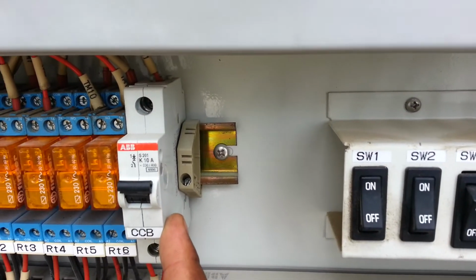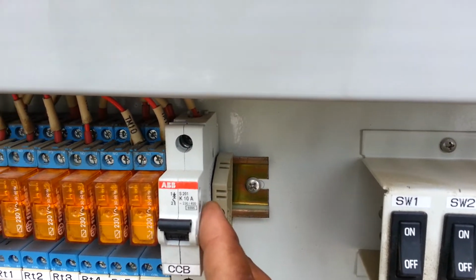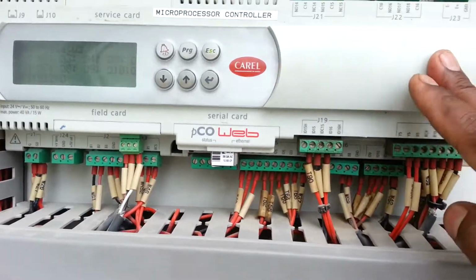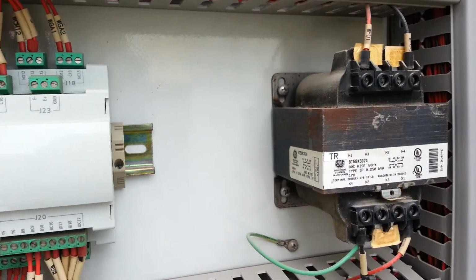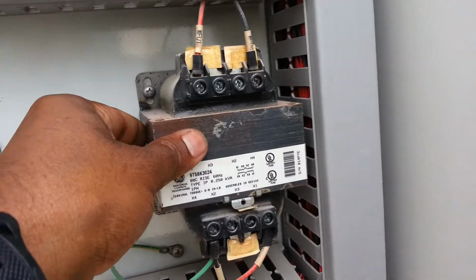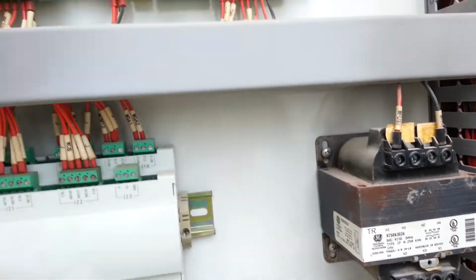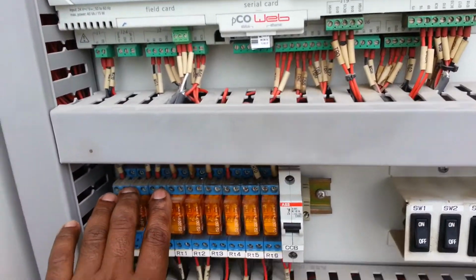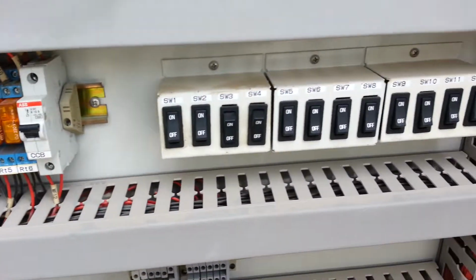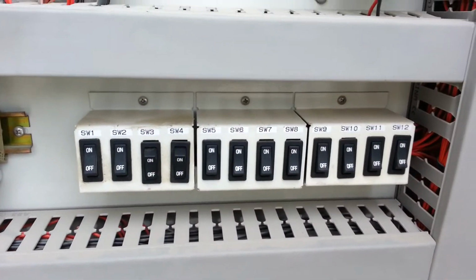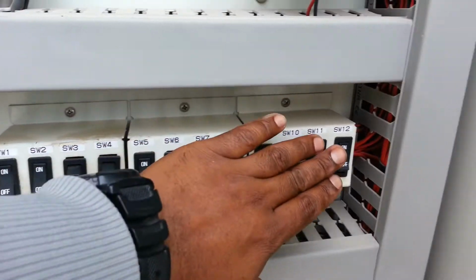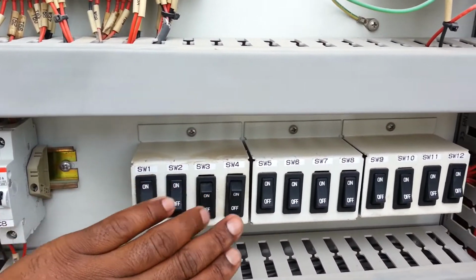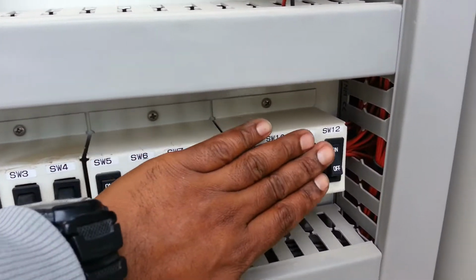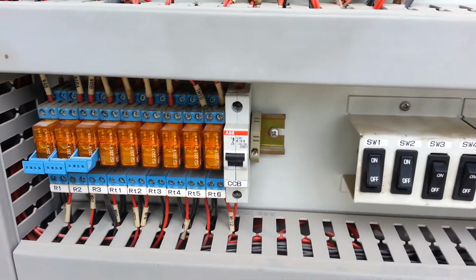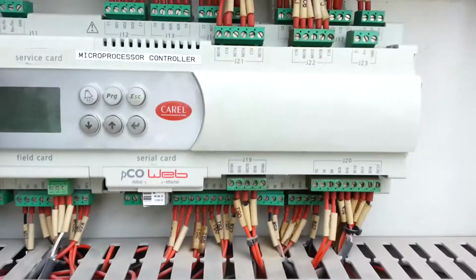And here is the MCB for this control, for this control transformer. This is the control transformer. It gives power to this display and this extension, and also to this relay. There is a switch here. We can manually turn the compressor on and off. And this machine is also connected with the BMS.